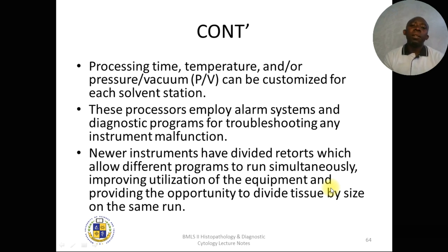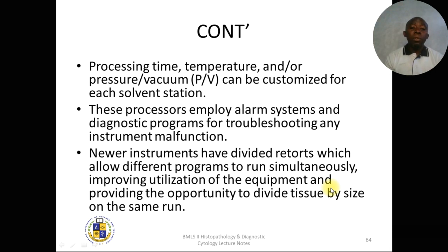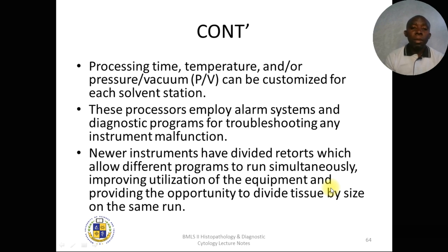Processing time, temperature, and pressure can be customized for each solvent and automatically set via the machine's interface. Students are encouraged to go to the lab for hands-on experience with tissue processors, as the profession is practical and it is important to actually operate these machines, not just view images.